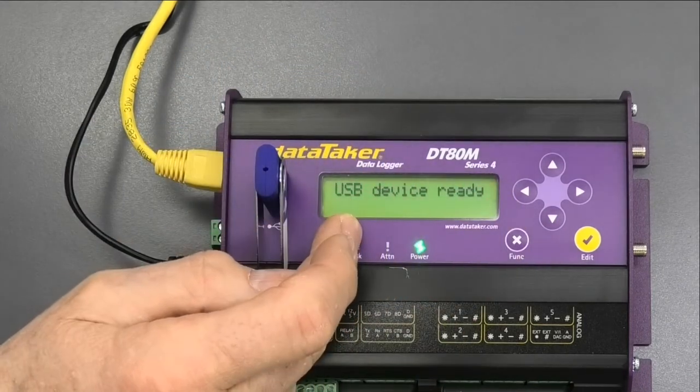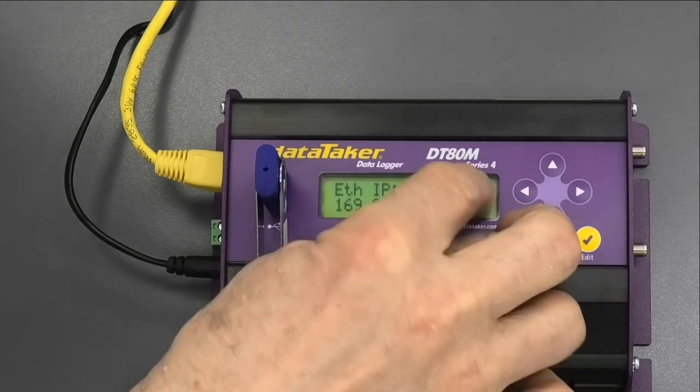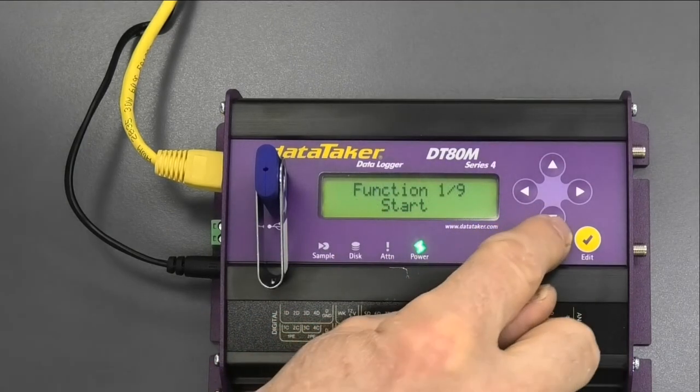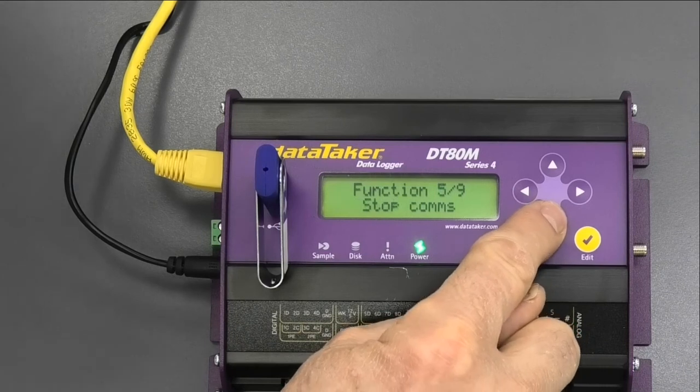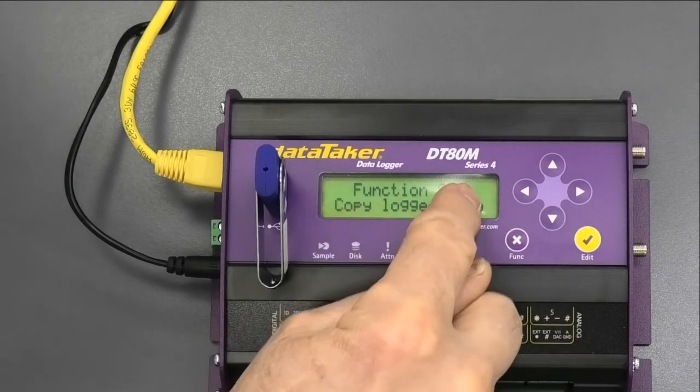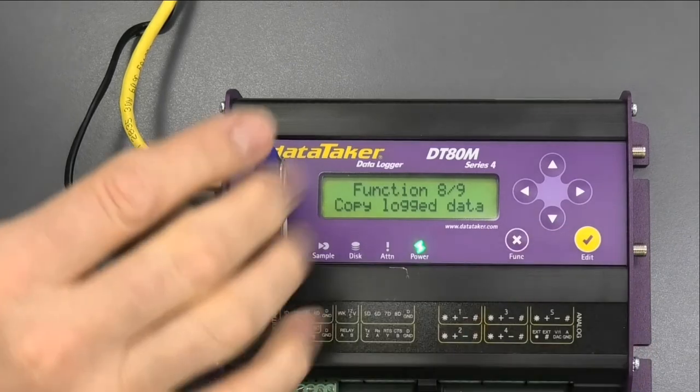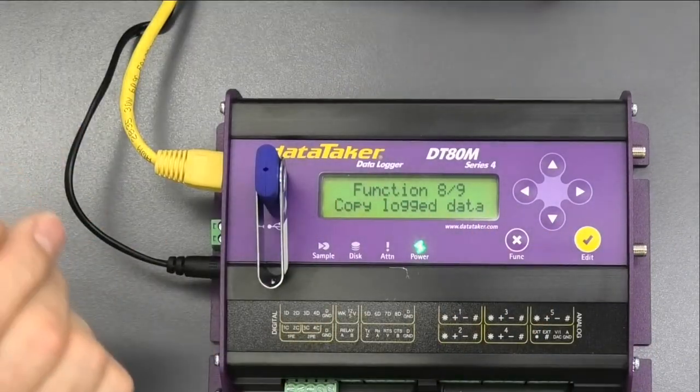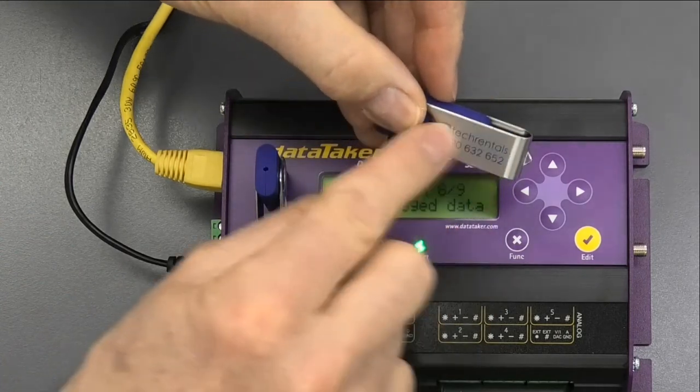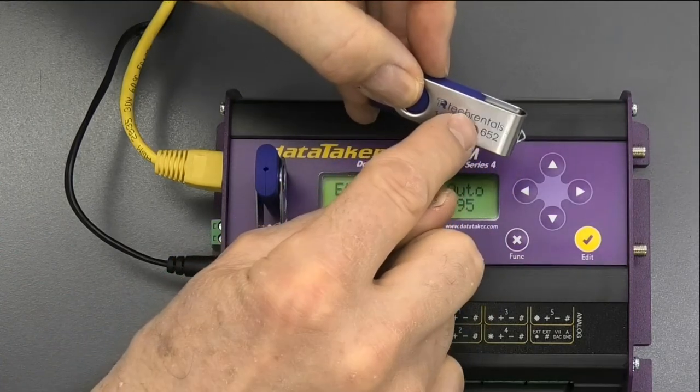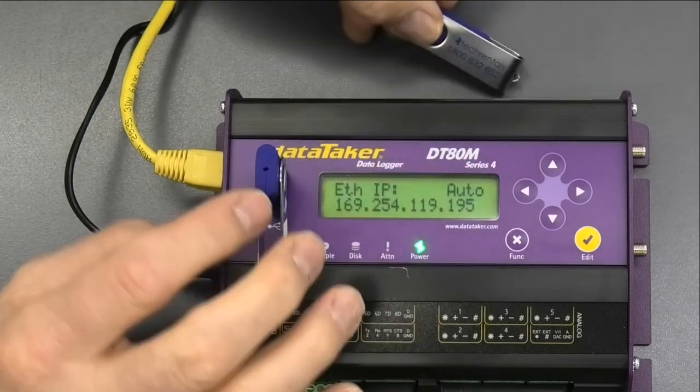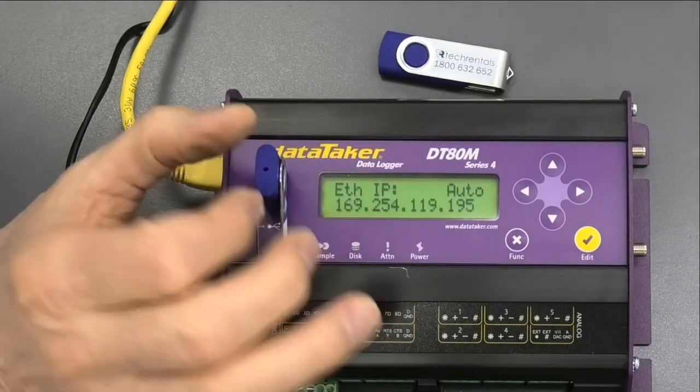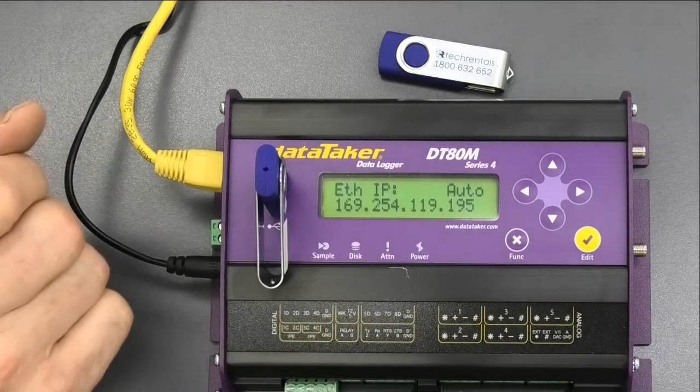That has only taken a couple of seconds. We can now go, if we were to download, we'd simply bring up, we hit this function key, and we can use up and down, and we can then go copy data, any stored data. So now that's ready to save data to the memory stick. It makes it very easy to use. However, if you use a standard 8GB memory stick, it will take up to 13 minutes for it to identify this stick. So the one we supply with it has been formatted in a way that the logger likes, so be aware of that.